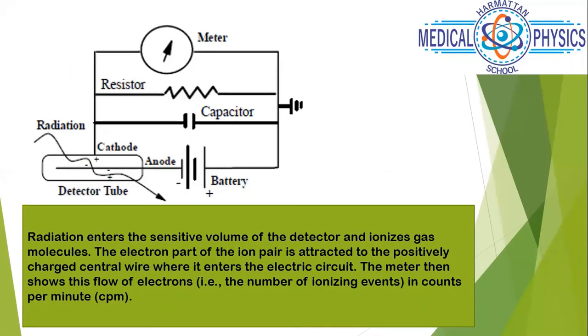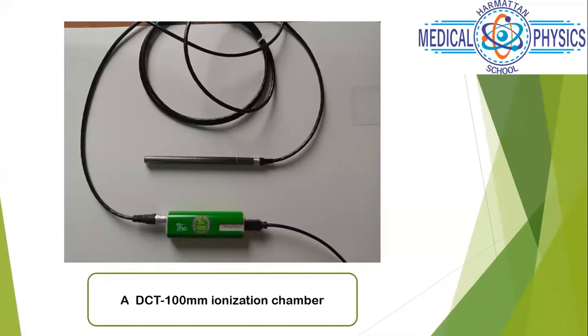Here is an IBA ion chamber — a DCT 100 mm ion chamber. The sensitive volume is the length along the chamber. This is quite expensive and we use it for dose measurements — for example, CTDI measurements. You want to get your dose output using your 16 cm and 32 cm phantoms, measuring at 12 o'clock, 3 o'clock, 6 o'clock, and 9 o'clock positions.